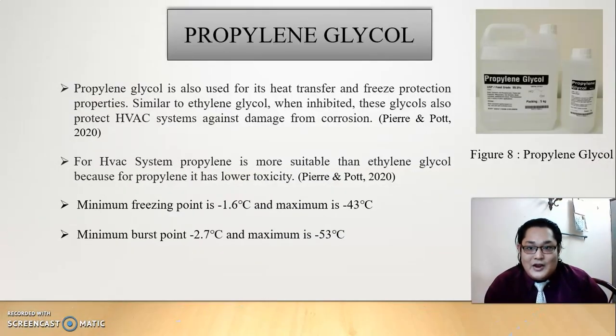Propylene glycol. Propylene glycol is also used for heat transfer and freeze protection properties, similar to ethylene glycol. When inhibited, this glycol also protects the HVAC system against damage from corrosion. For HVAC systems, propylene glycol is more suitable than ethylene glycol. Why? Because propylene glycol has lower toxicity.